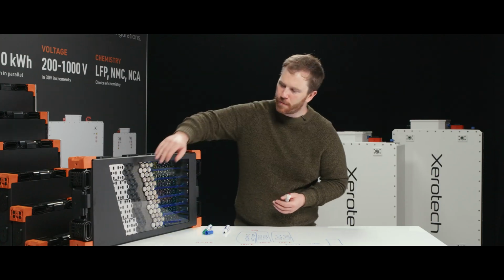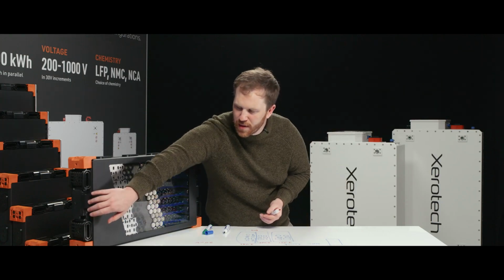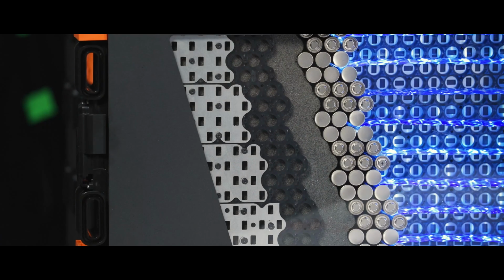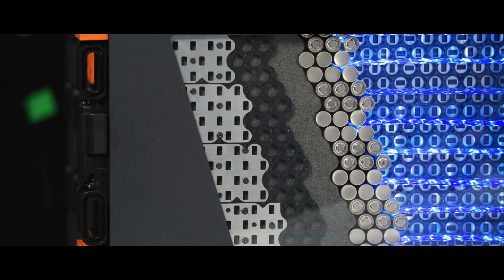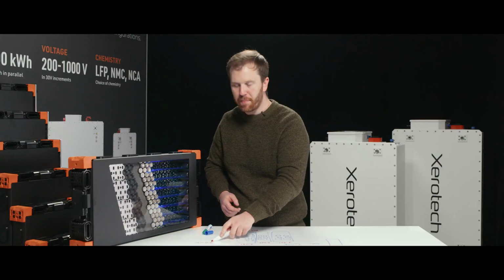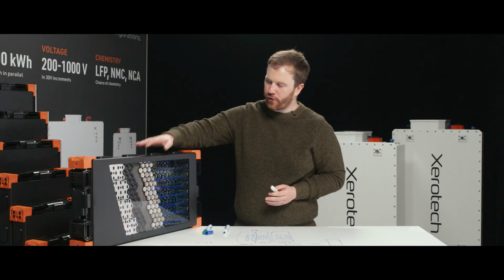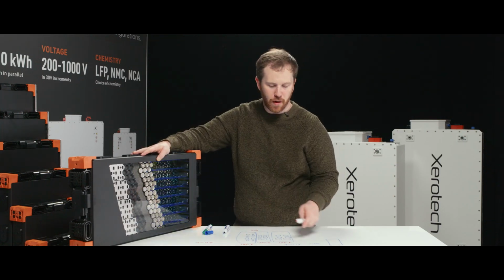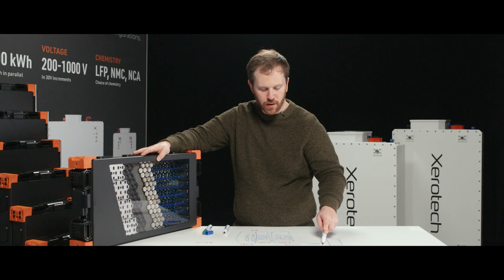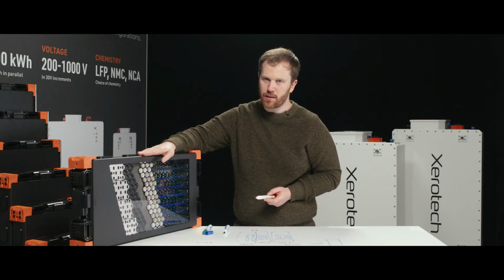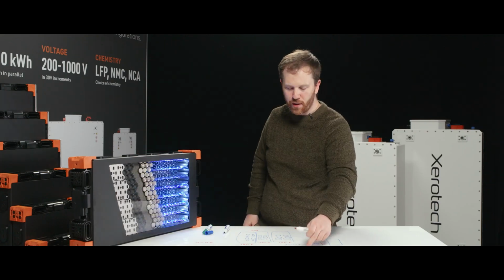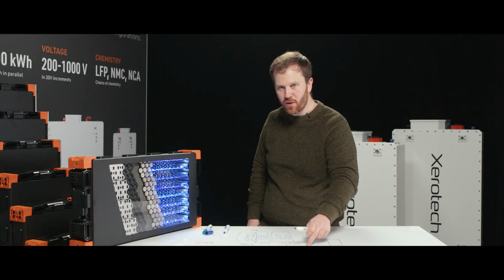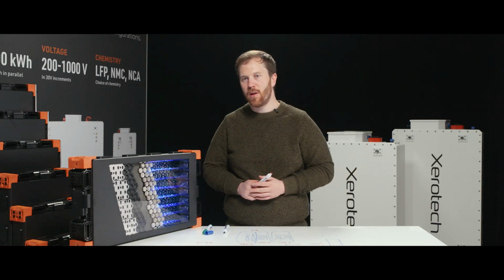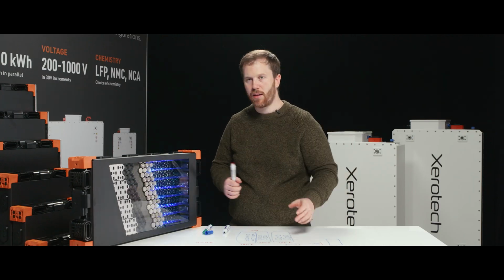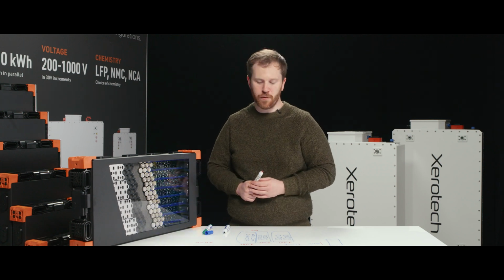So that's virtually what every single BMS on a module level is doing. It's measuring voltage and temperature, and it's doing balancing. So that's safety at a module level to avoid these critical issues with the cells. So if you keep a cell within its voltage limits, within its temperature limits, it's generally going to be okay. And it goes without saying that you're not over discharging or overcharging the battery cells.